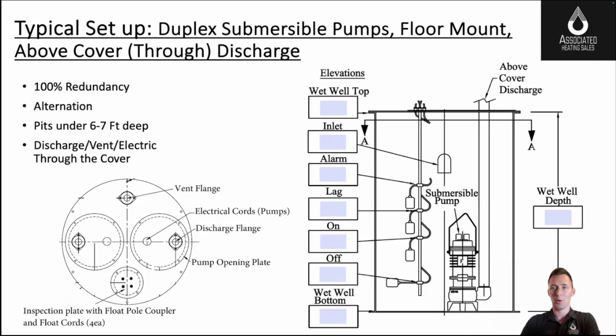So for sewage or groundwater, you have a gallon per minute flow that you've designed for. Each pump in these systems can do that full flow. So you could technically operate on one pump while the other pump's being fixed or a new pump's being ordered. And that's most typically what we see in commercial buildings because we just don't want to be down. We don't want to shut all the fixtures down, things like that.